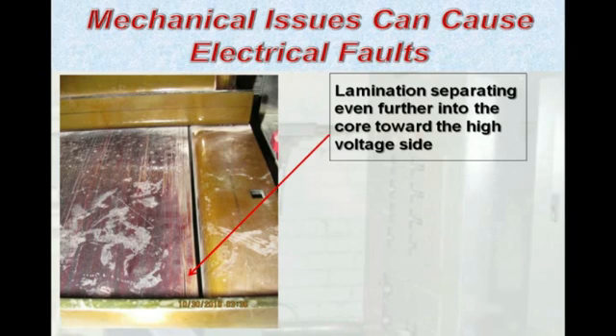From a different perspective, or a different camera angle, you can see deeper into the core, the laminations were already beginning to separate within this core. And when this happens, you no longer have that bond between the pieces, and with the expanding and collapsing magnetic field, these laminates begin to vibrate. When they vibrate, they generate ultrasonic emissions, and they cause thermal heating. So this is getting closer to the source of what the issue is here.